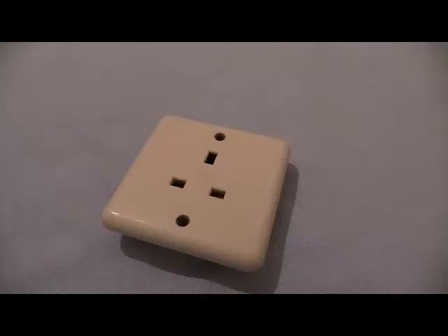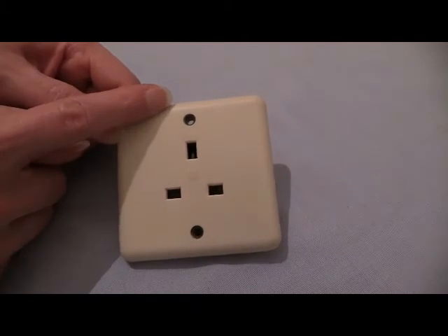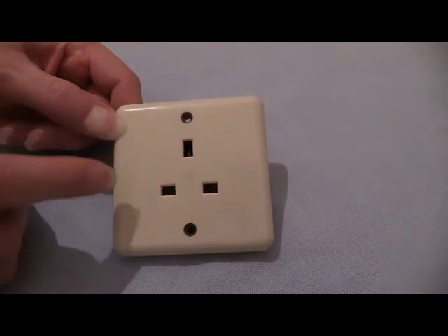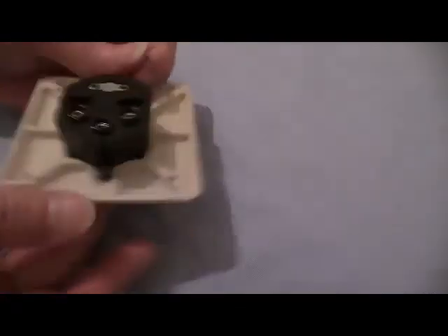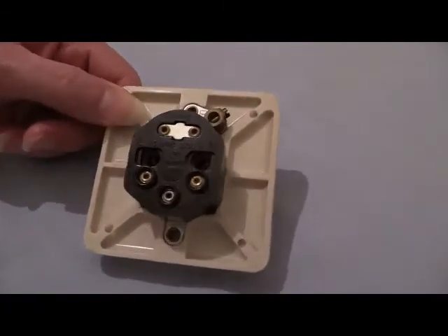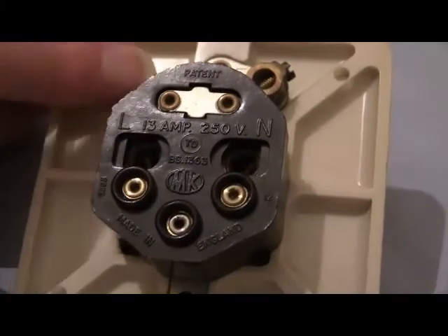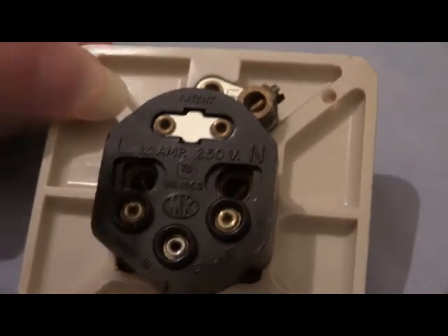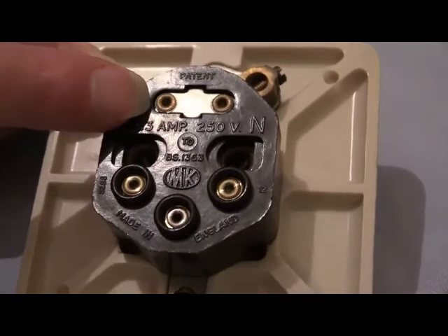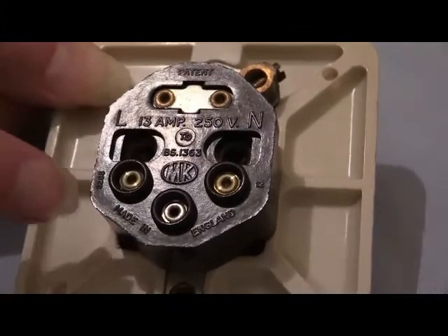That is a single socket flush mount, 13 amp, which is standard BS1363. It's a bit of an old one — you can tell by the fact that the fixing screws are down the bottom and up the top. Modern-day sockets would have fixing screws to the left and to the right. Let's flip it over and have a look. On the back we've got all the detailings — oh look, it's an MK. It says 13 amp, 250 volts, although you'd be lucky to get 250 volts in your house. This is a maximum power voltage rating; it would normally be around about 240 volts. Just down there it says British Standard 1363, made by MK, and of course made in England.